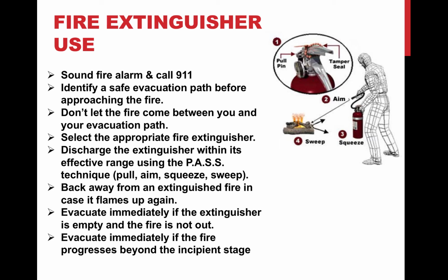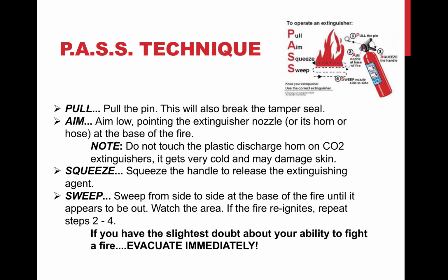Select the appropriate fire extinguisher. Discharge the extinguisher within its effective range using the P.A.S.S method, which means pull, aim, squeeze, and sweep. Back away from an extinguished fire in case it flames up again. Evacuate immediately if the extinguisher is empty and the fire is not out, or if the fire progresses beyond the incipient stage. In other words, don't be a hero and try to put out a fire that you have no way of beating. So the P.A.S.S technique, again: pull, aim, squeeze, and sweep.